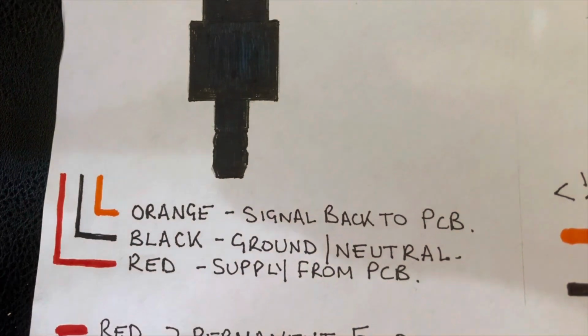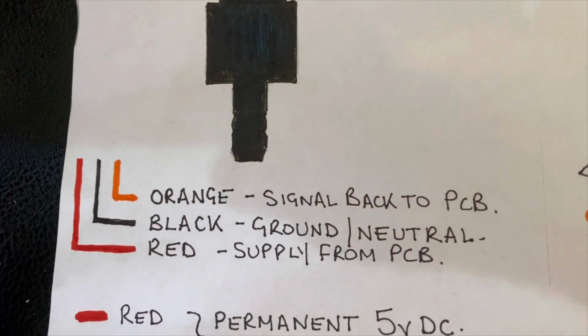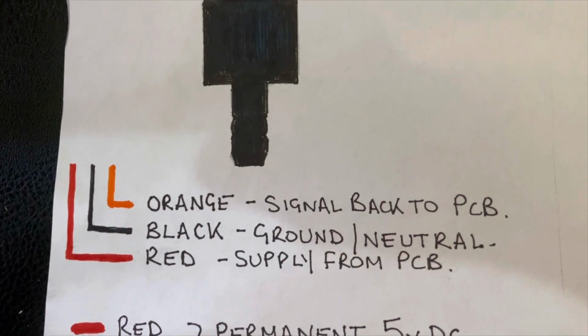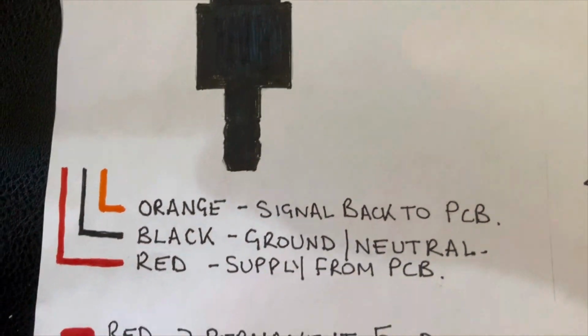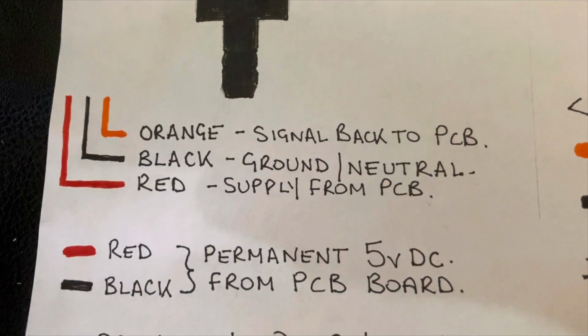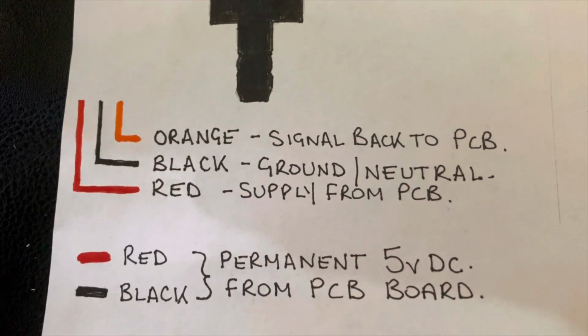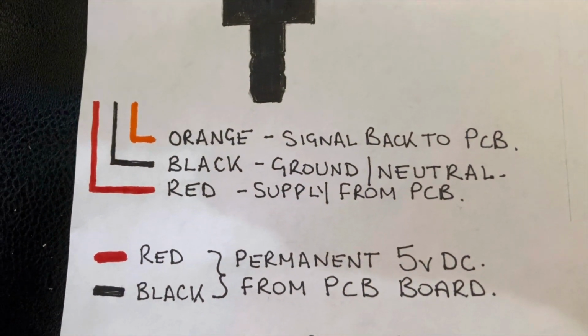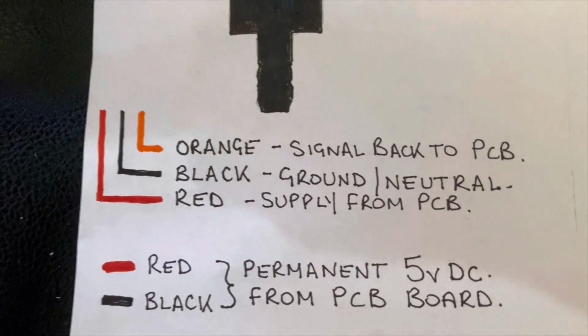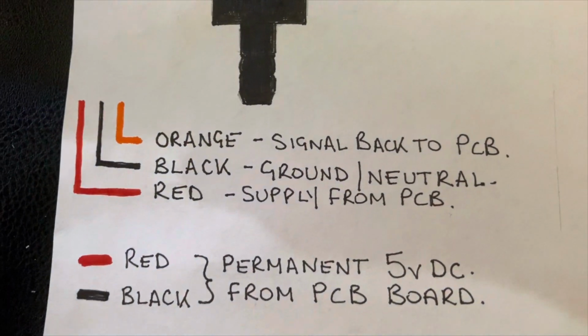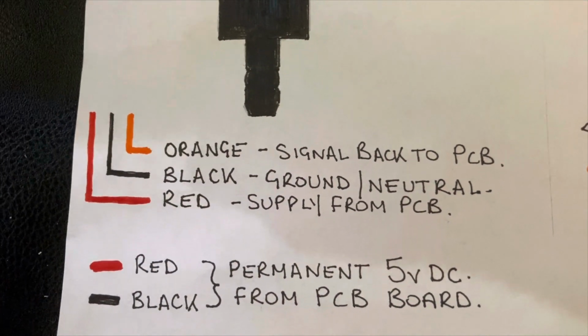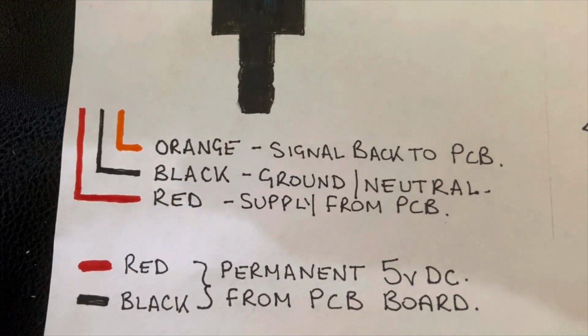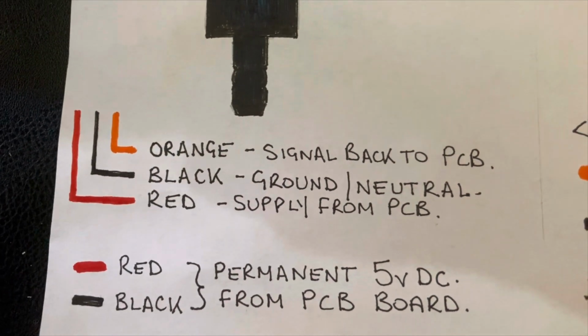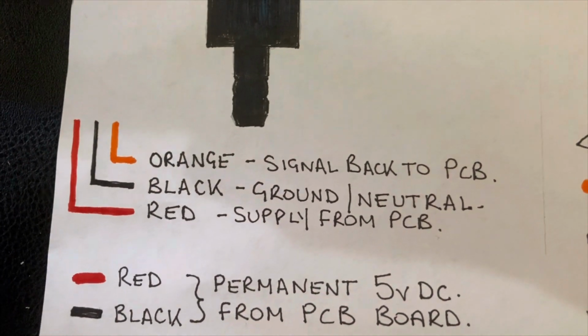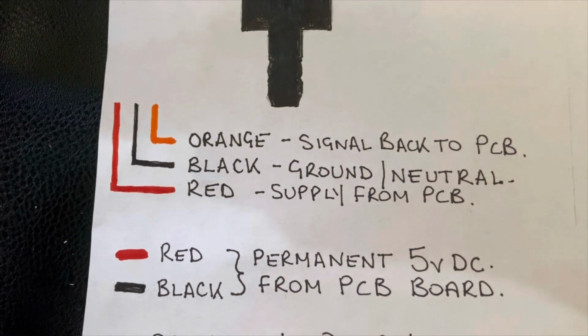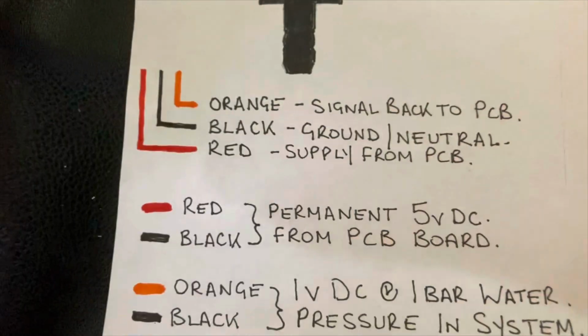So as you can see, we've got an orange, a black and a red. The orange is the signal back to the PCB, the black is the ground or the neutral, and the red is the supply from the PCB. So what I've done here, I've noted between the red and the black you'll get a permanent 5 volts DC from the circuit board at all times. So if you're testing between red and black, expect 5 volts DC on your multimeter. That should always be there. If the power's on, the fusing to the PCB is okay and the PCB is working, you'll get 5 volts.